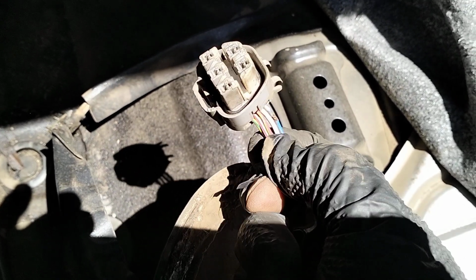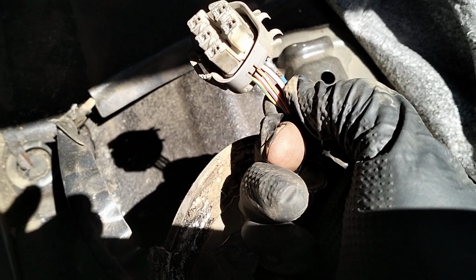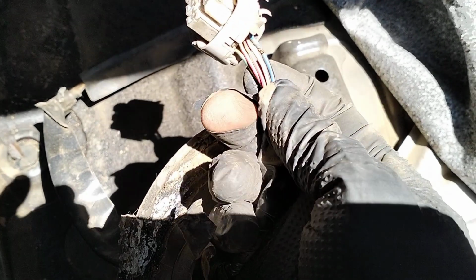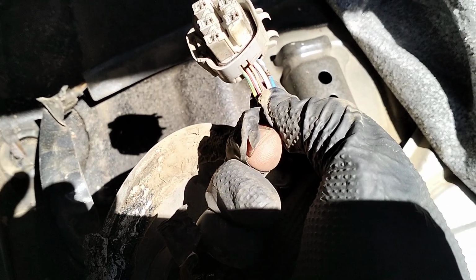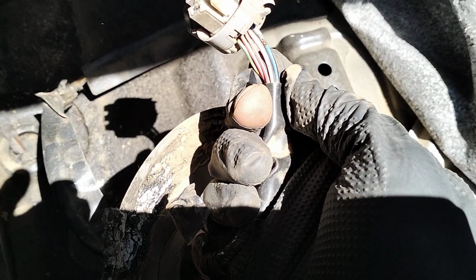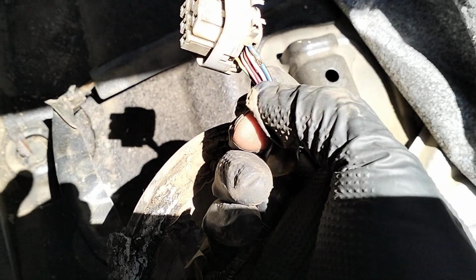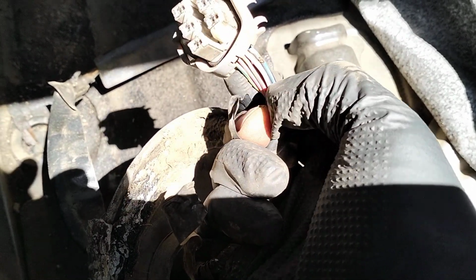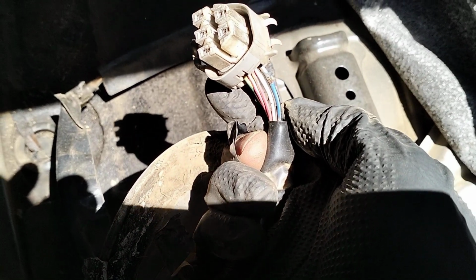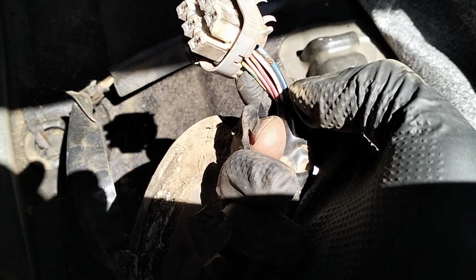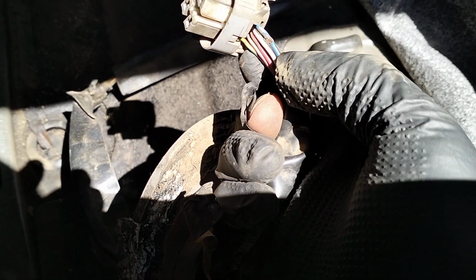If you want to probe wires like this, you need to use proper probes. I suggest using the Pomona pin probes. Those are the best I've seen in the market, and they make a very tiny incision on the insulation, and when you're done and remove it, it actually closes itself up. You don't even have to do much, and if it's too big, you just put a bit of liquid electrical tape and you're done. This is poor workmanship, should never be done. You probe these two wires, and then we take the capture of the powers and grounds at the pump.